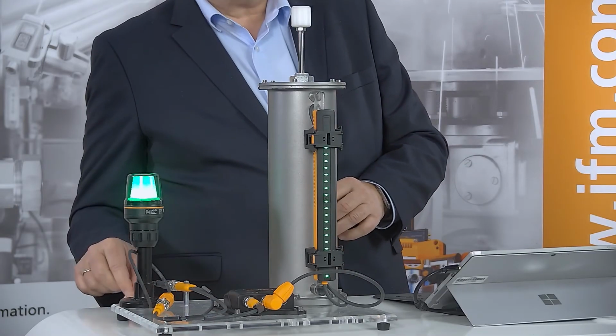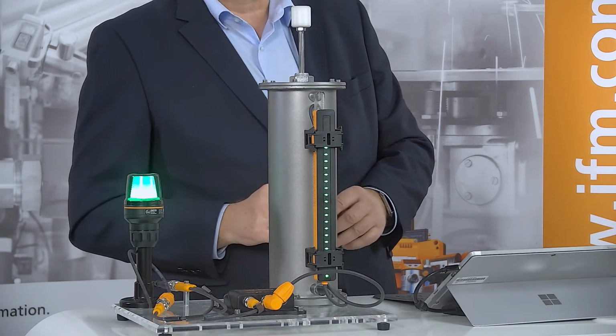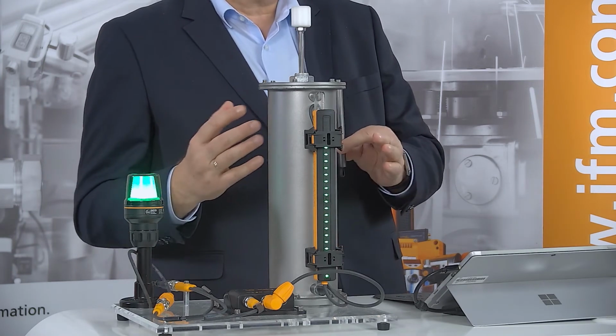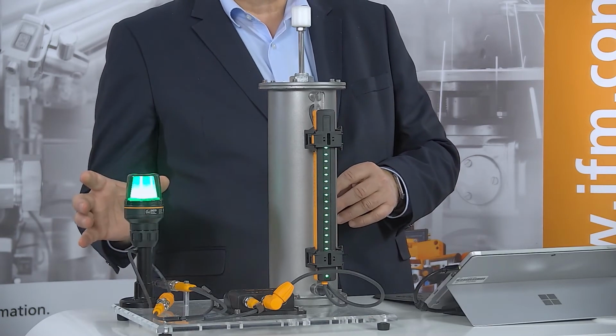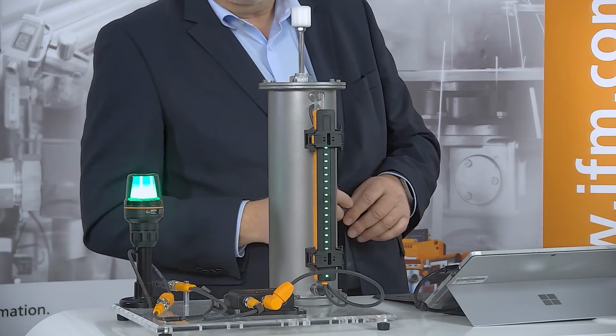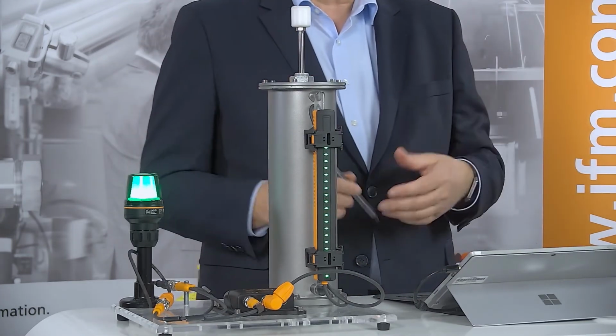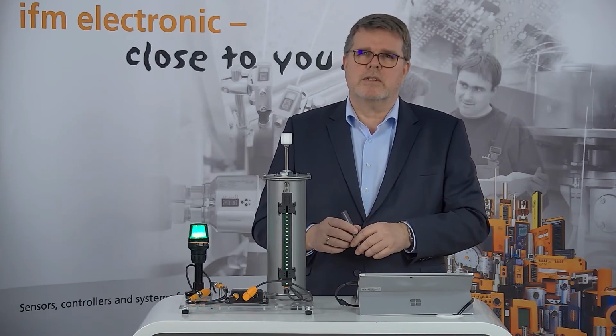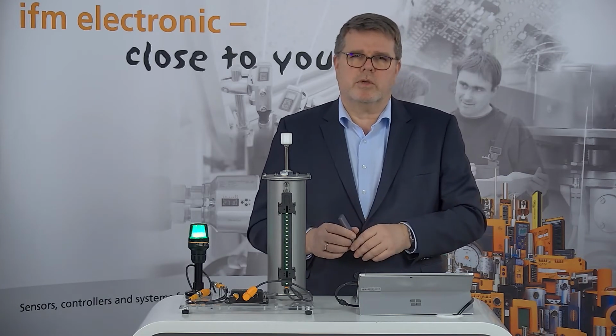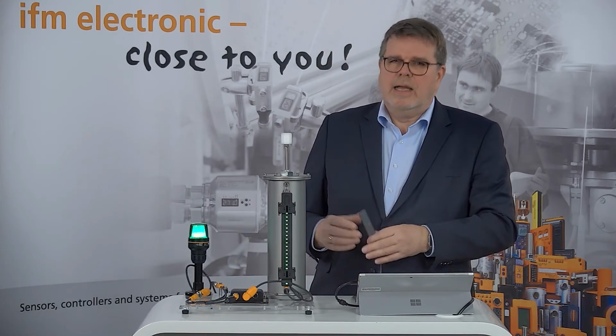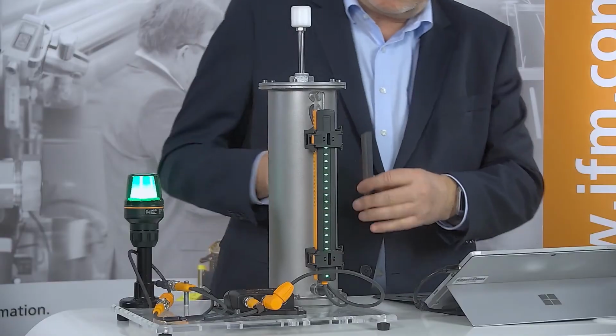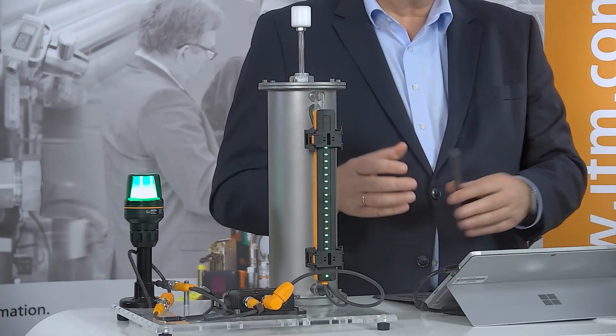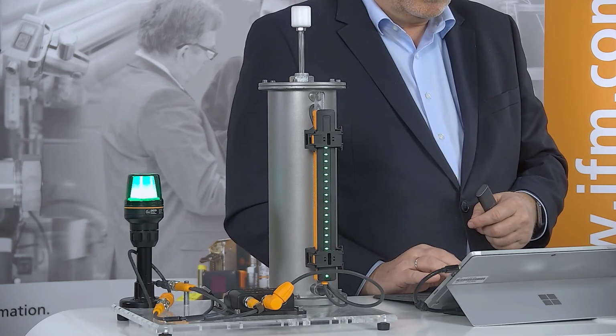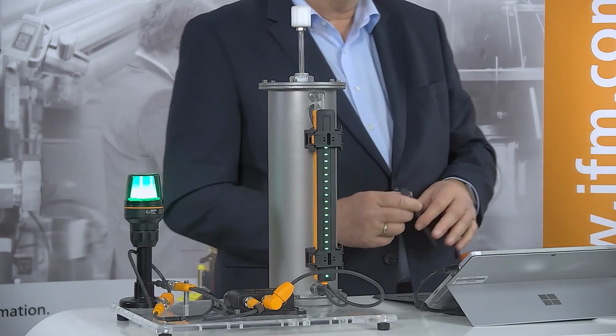That's exactly what the I/O key does. It's just connected to power, and in between the power connector and the I/O key there's also an indication light, which tells the people at the road construction whether the level in the silo is okay or not. You can choose from one of 10,000 I/O-Link sensors available on the market. We prefer the orange ones, like here, to detect the level in the silo or tank.